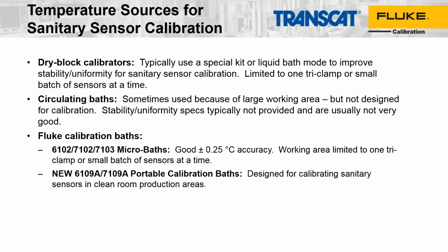but the tanks are fairly small, and we looked at those and realized that there are some good design improvements that we could incorporate. And so we came up with a newer model line, the 6109A, 7109A Portable Calibration Baths. They were designed specifically to accommodate sanitary sensors, but they are also, in general, a calibration bath that can solve a lot of the problems we've been talking about.